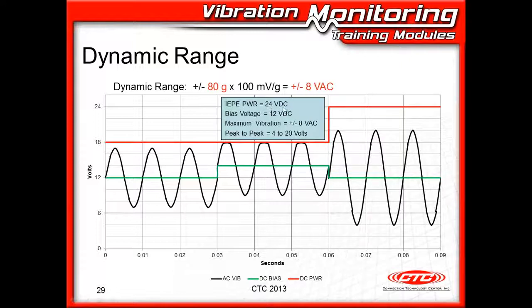On this last segment, I've increased the power supply to 24 volts DC. And that's a little more typical of what you'll find, provided you're not using one of the older battery-operated supplies. If you've got your data collector, your condition monitoring system, 24 volts is fairly typical. I've put my bias voltage back in the center of the range at 12 volts DC, and I've gone with an 80G sensor providing plus or minus 8 volts AC. So here you can see that, again, I've got a very happy sensor. I'm swinging from 4 to 20 volts, my min to max vibration, and I'm not clipping anything off.